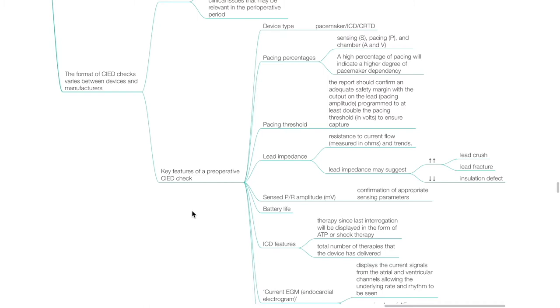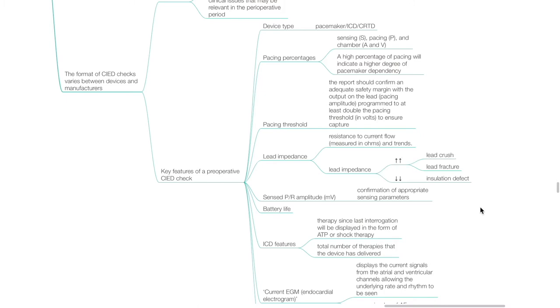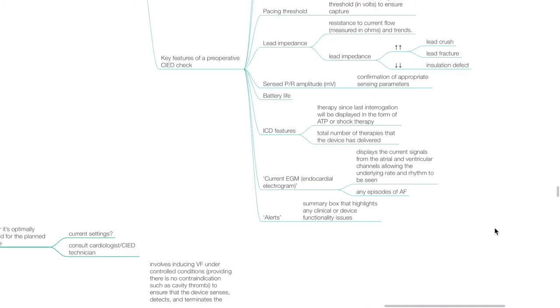Key features of a preoperative CIED check include: device type (pacemaker, ICD, or CRTD); pacing percentages (sensing, pacing, and chamber); pacing threshold — the report should confirm an adequate safety margin with pacing amplitude programmed to at least double the pacing threshold to ensure capture; lead impedance — increased impedance may suggest lead crush or fracture, reduced impedance may suggest insulation defect; sense/PR amplitude confirming appropriate sensing parameters; battery life; ICD therapy since last interrogation displayed as ATP or shock therapy; current endocardial electrogram; any episodes of AF; and alerts highlighting clinical or device functionality issues.